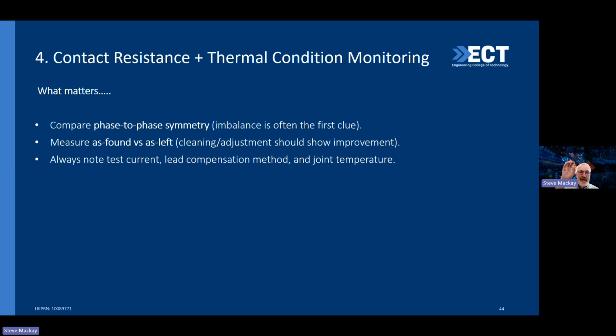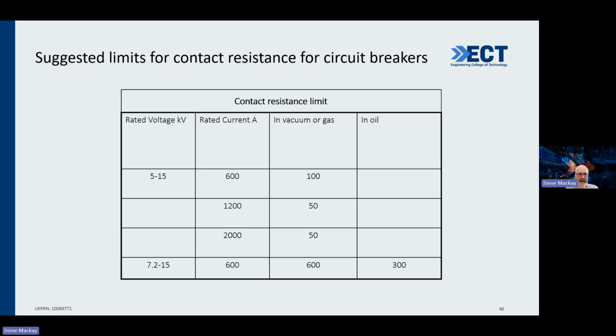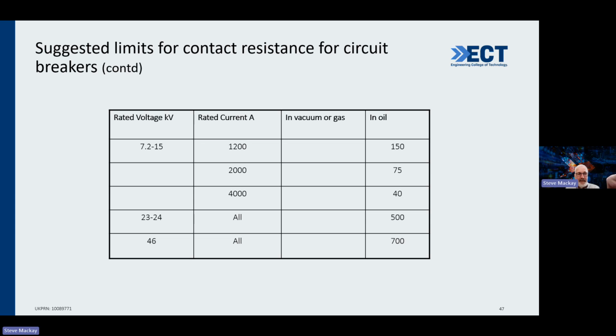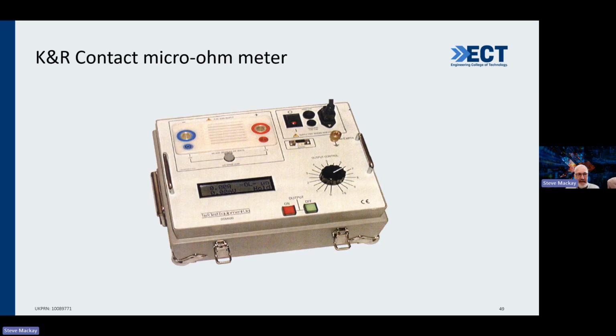Lead compensation method is obviously really important. What does lead compensation method mean? Yeah, thanks. Within adjustments, calibration limits. Thanks very much. Unfortunately time's tight, so I'll surge on here. But lead compensation method is when you're injecting current in and you're measuring, you don't want to have a bad measurement because the leads of your measuring instrument are actually contributing to some of the voltage drop. So you want to give the actual measurement as accurately as possible. So it's quite useful to tell what lead compensation you're using. These, by the way, are all micro ohms. I'm not going to worry about these.